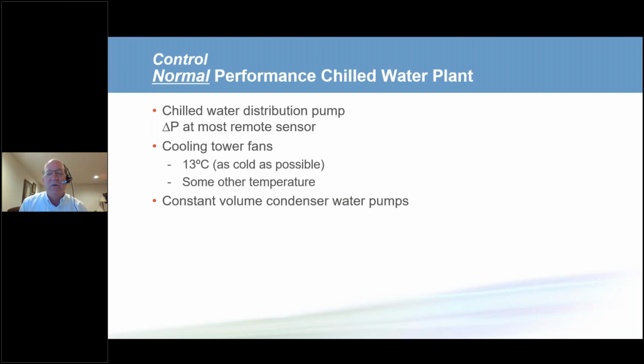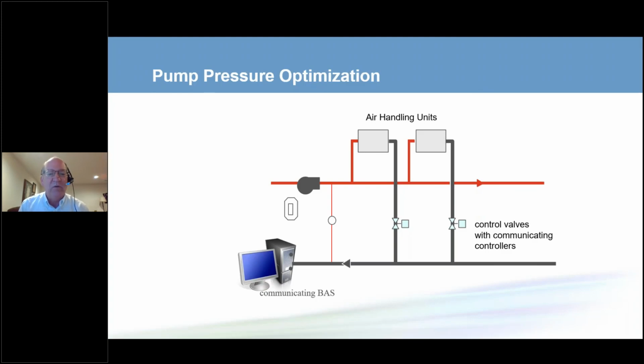And we can get cooling tower water temperatures. And then we often have constant volume, constant flow condenser water pumps. Let's look at some options. The first thing we're going to talk about is what's called pump pressure optimization.